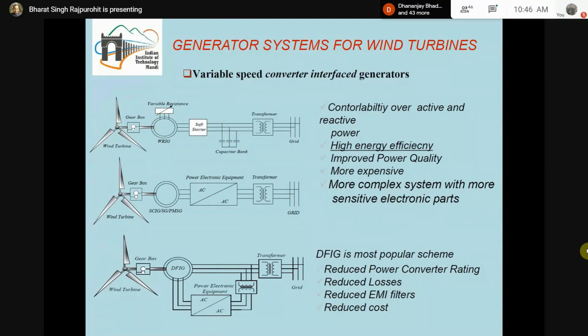So when the rotor power is extracted, the control of the speed is now with this rotor side power electronic converter. So this scheme becomes a variable speed scheme. In certain cases, power can also be fed back to the rotor, and then the speed can be taken above the synchronous speed. So that is also possible. Subsynchronous, below synchronous speed, or supersynchronous, above synchronous speed, all such operations are possible while controlling this rotor side power electronic converter, and hence this machine can work as a generator in a very wide range of speed above and below synchronous speed, and this power is utilized and not wasted. So this scheme becomes very important.